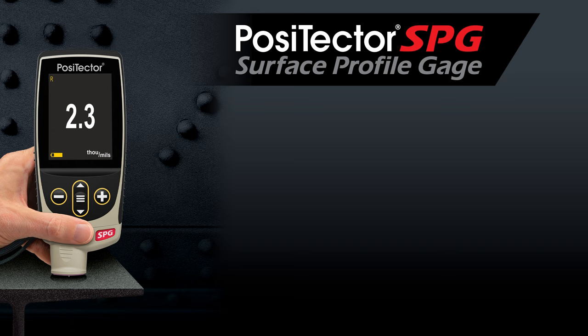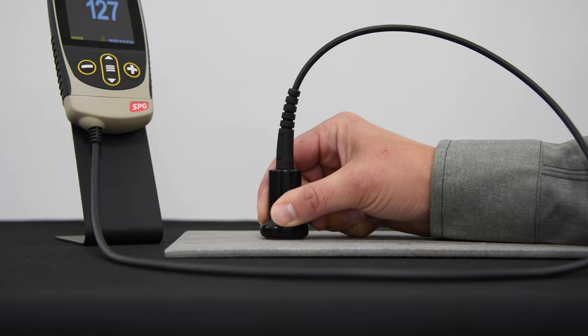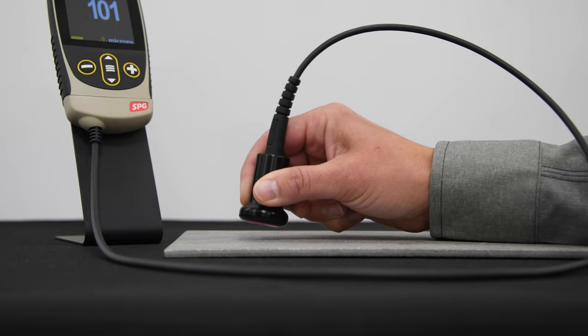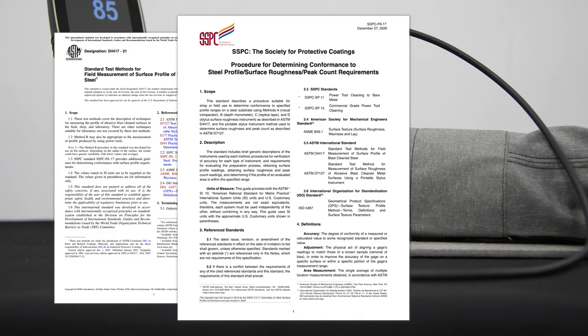The PosiTector SPG surface profile gauge is popular for users who want a fully digital test with zero per test cost. The digital depth micrometer is fitted with a fine pointed probe to measure and record peak to valley surface profile heights in accordance with ASTM D4417 Method B and SSPC PA17.